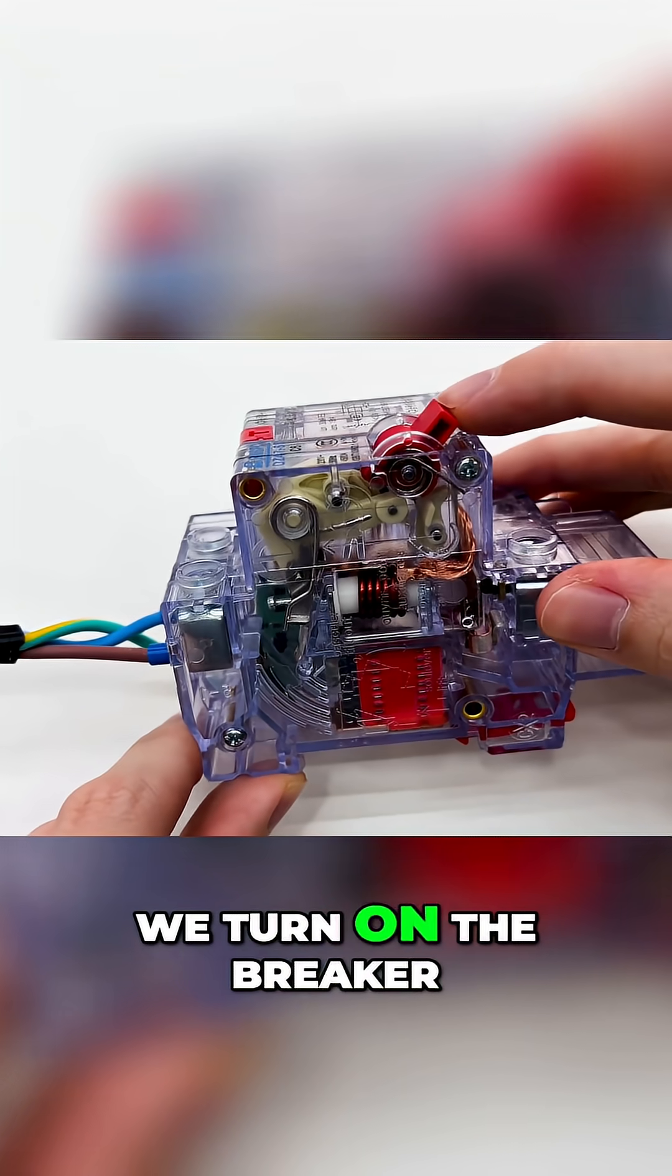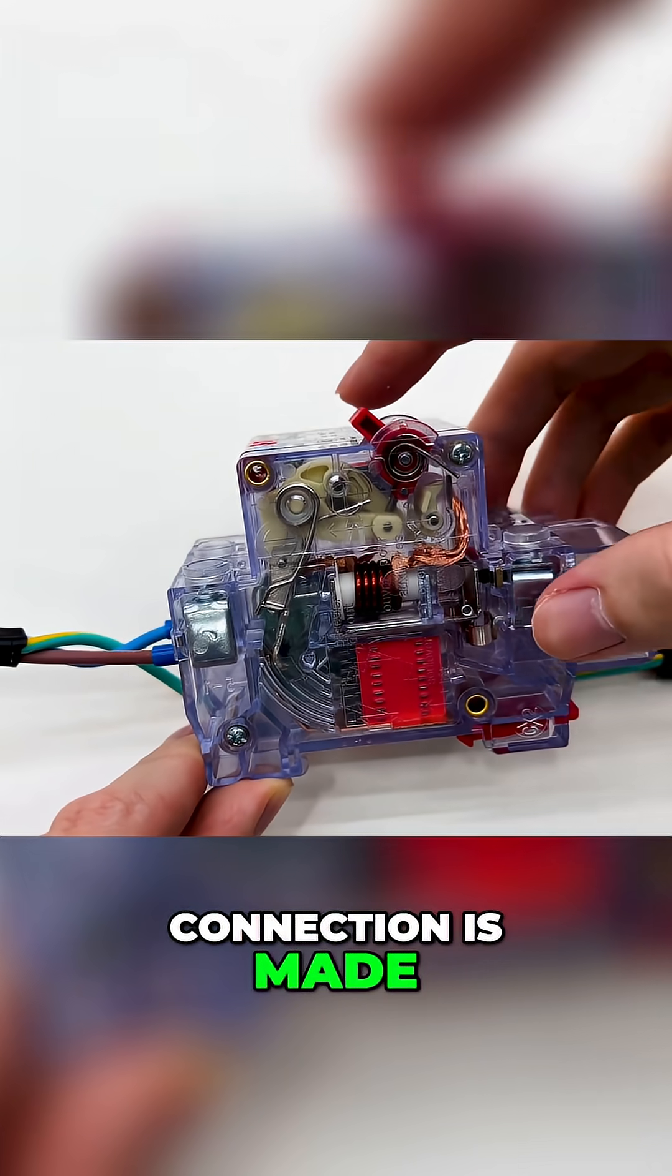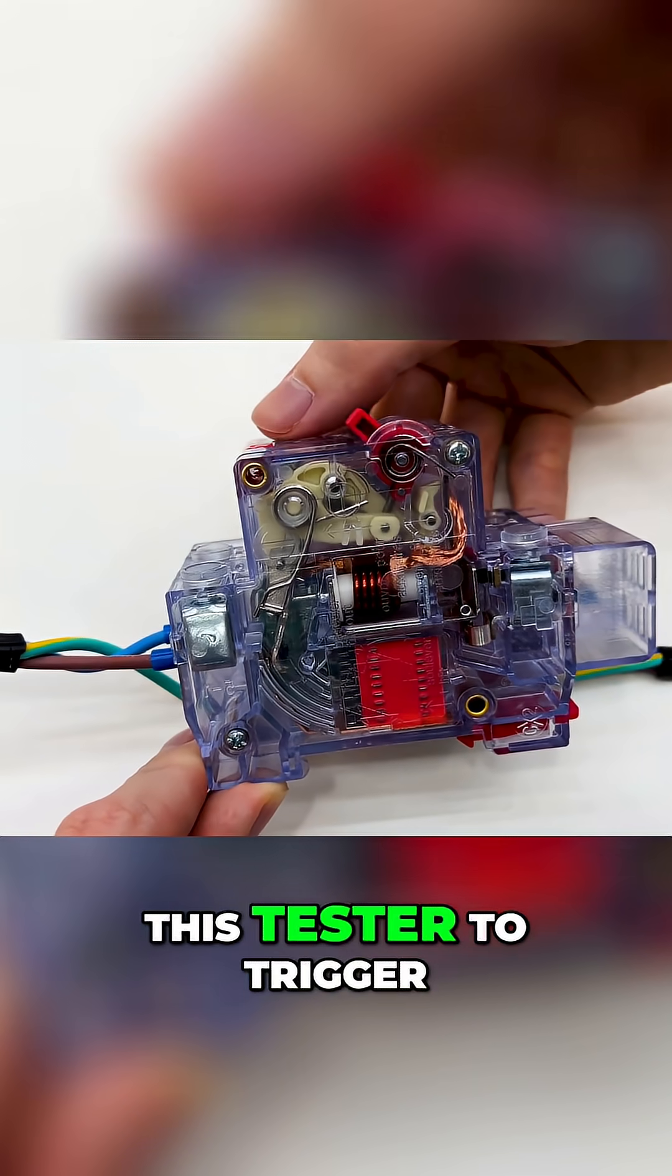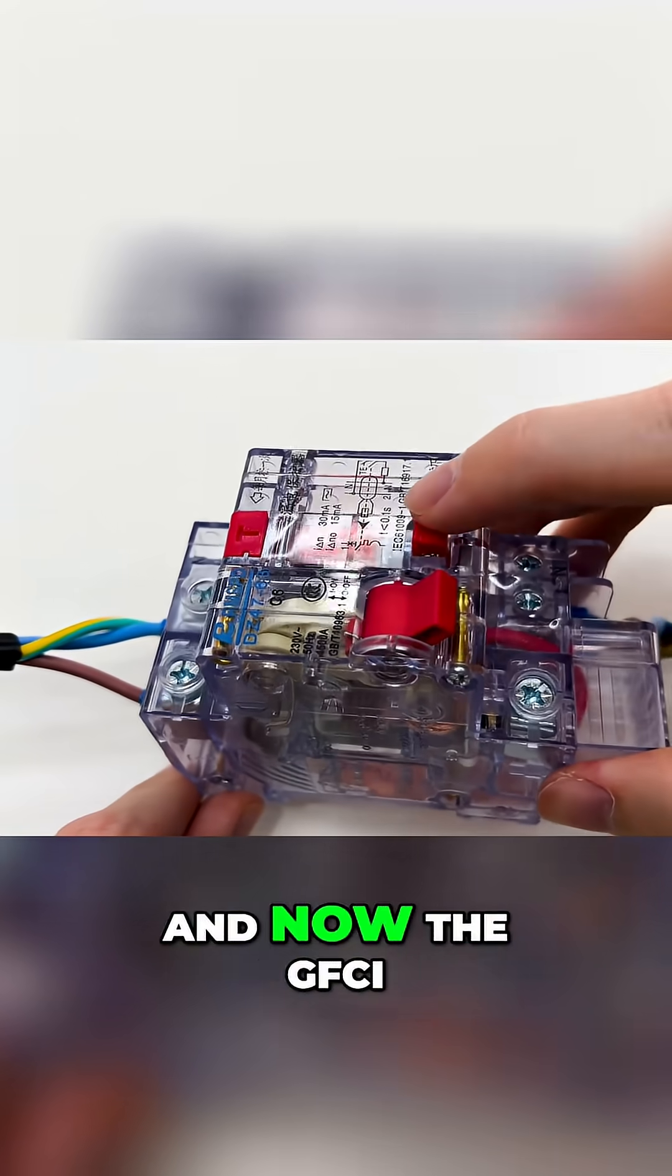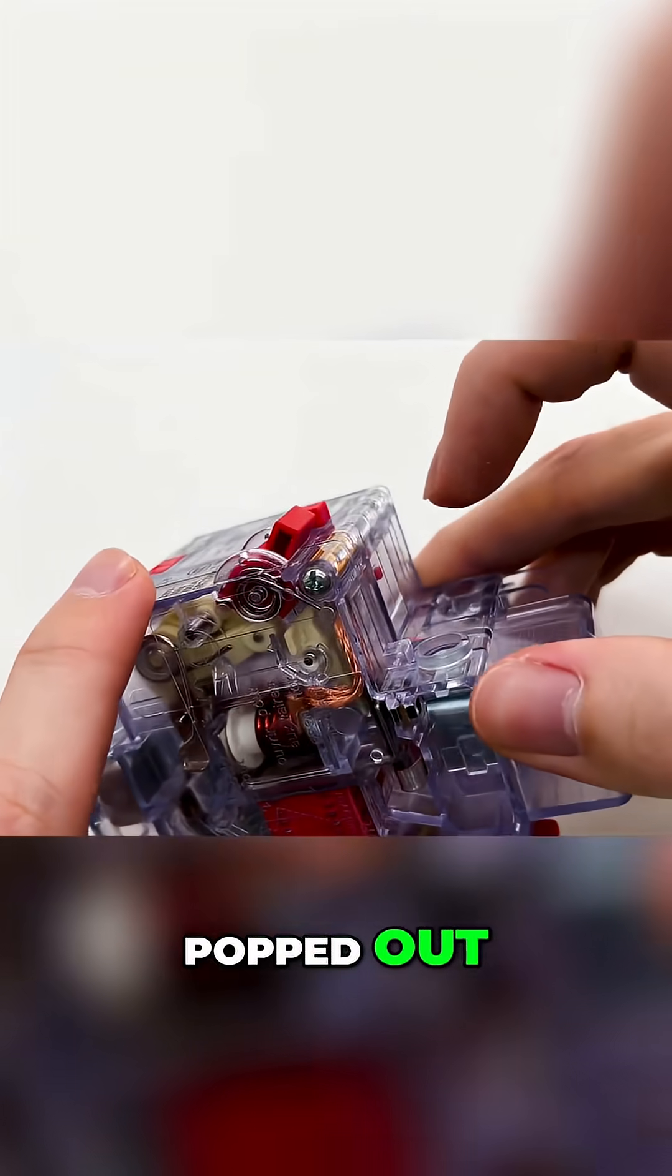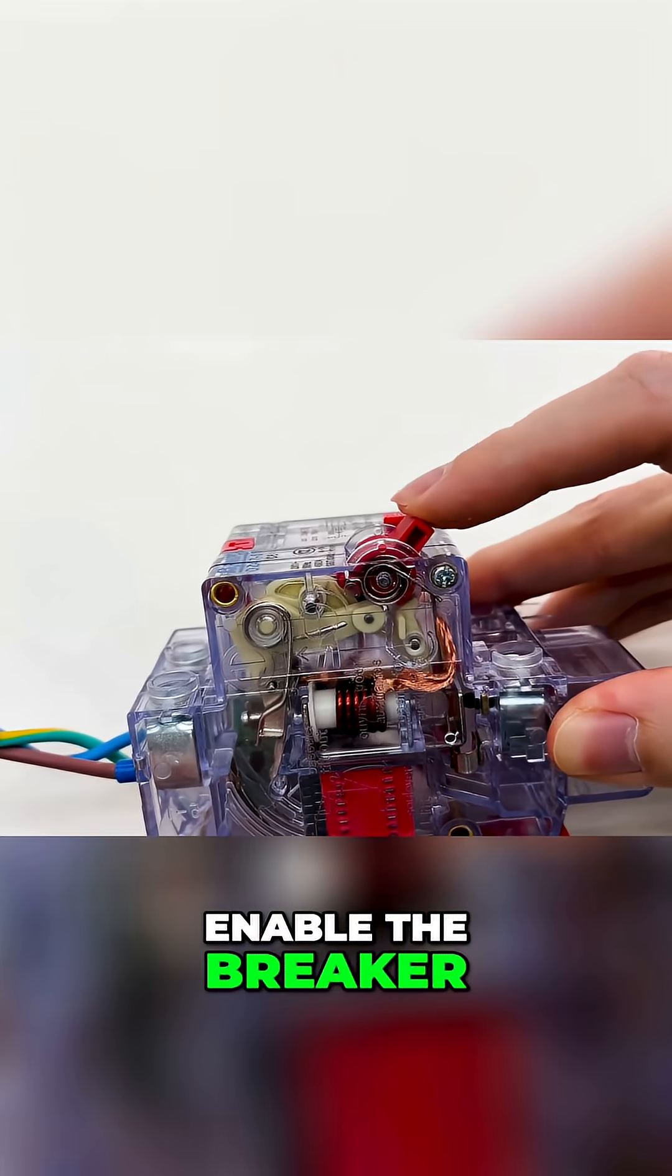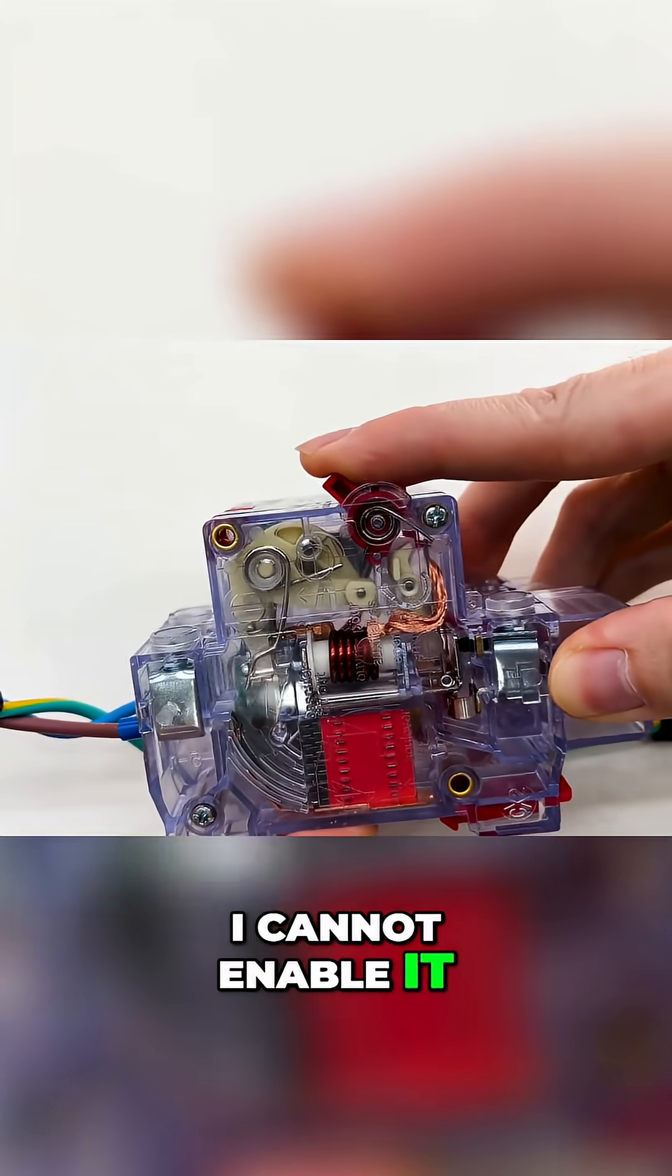We turn on the breaker, connection is made, and I will use this tester to trigger the breaker. You can see it shut down and now the GFCI popped out. Now when I try to enable the breaker I cannot enable it.